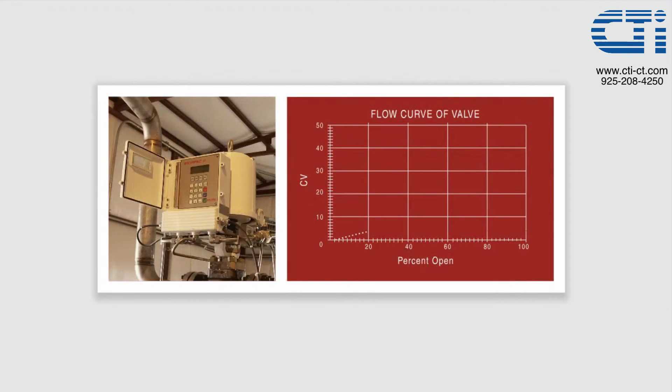The StarPak accurately measures the flow over the entire range of the valve. When each StarPak is built, its flow rate is measured through the valve from fully closed to fully open. This flow curve is then loaded into the onboard computer so that StarPak accurately knows the flow rate at any opening.